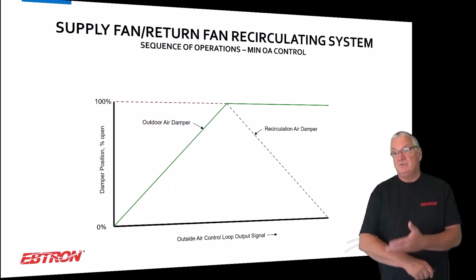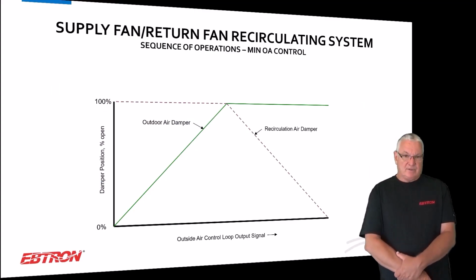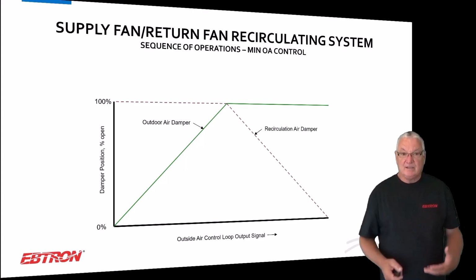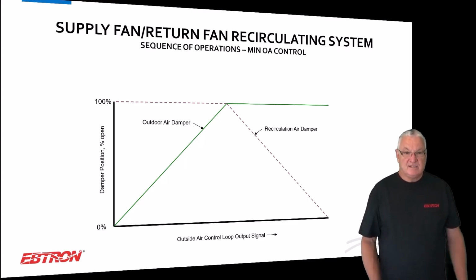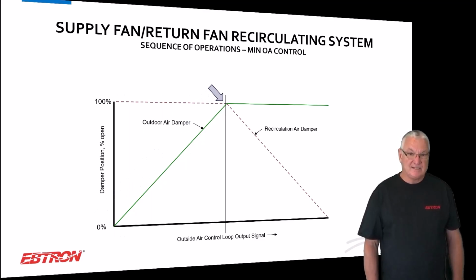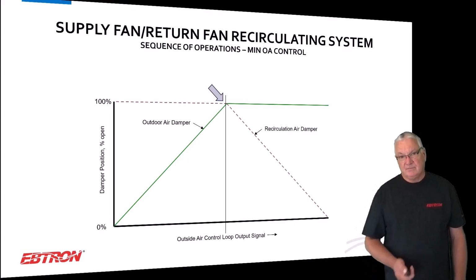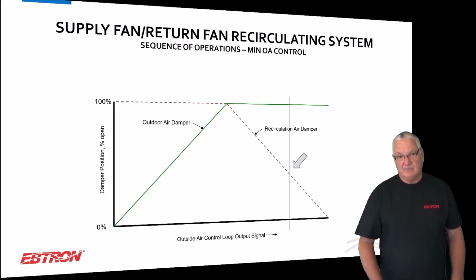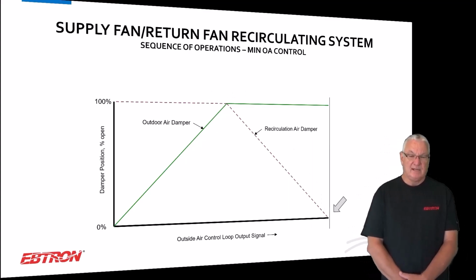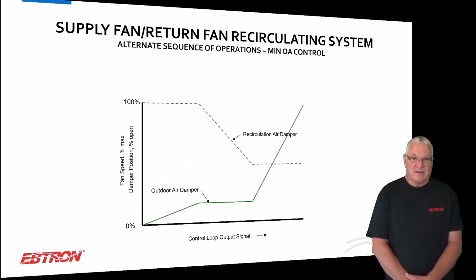we prefer that you sequence your dampers for the outside air control and not do an overlapping strategy, or just use the outside air damper. There's a number of reasons for that, but I'm going to tell you what we like to do. What we like to do is simply sequence them. So we start by first opening the outdoor air damper to maintain set point, with the recirc air damper fully open, and then if we still need more outside air, we will close the recirc air damper. Okay, so that's the strategy there.